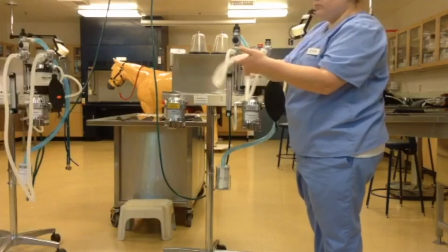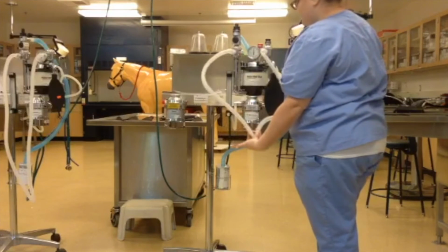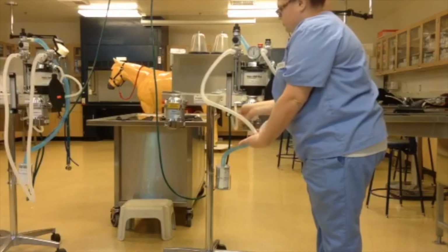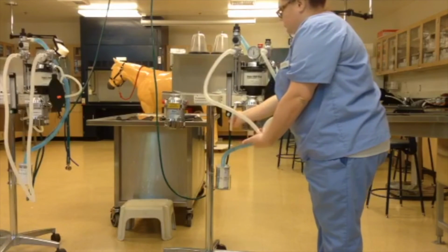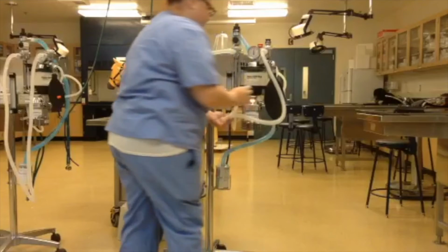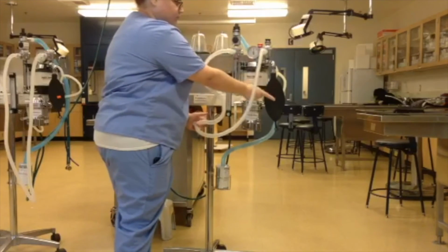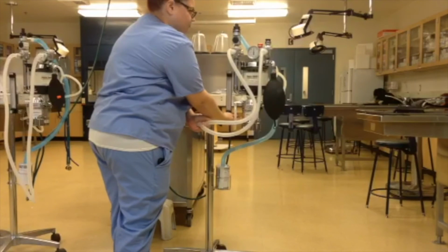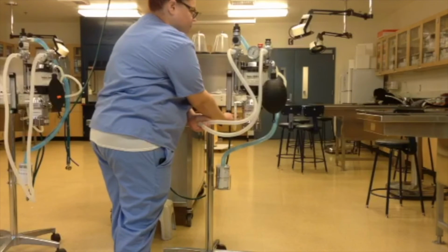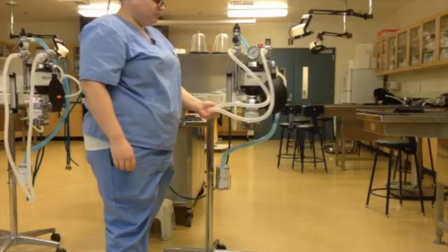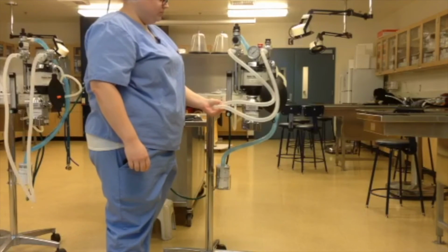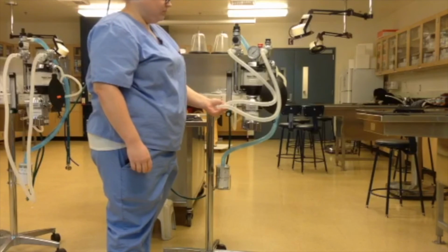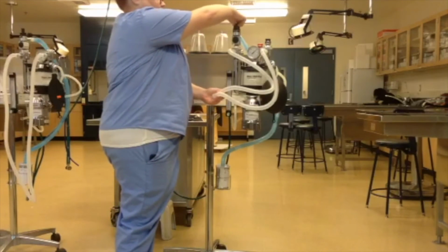Now I'm connecting the Y tube and placing it into the palm of my hand. Now I'm going to be watching the pressure manometer. Now I'm pushing the oxygen valve so that I can have oxygen flow and fill the reservoir bag, and I'm waiting for that pressure manometer to reach 20 centimeters. Then I count for 10 seconds to make sure that there are no leaks within the system.